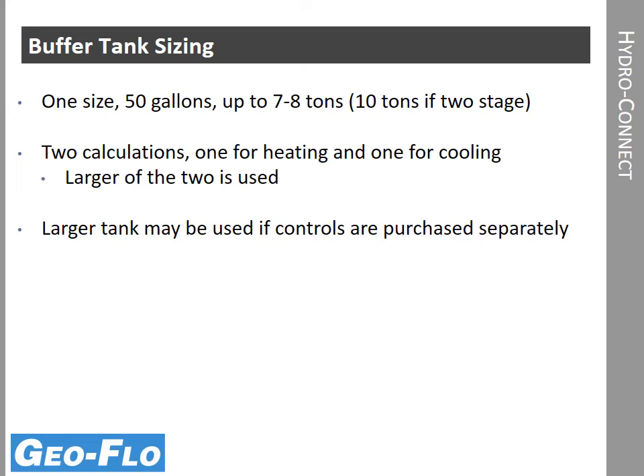So one size handles really a wide variety of applications. It's larger than what we might need for, say, a 3-ton heat pump, but it certainly doesn't hurt anything to have a little bit more storage. The buffer tank itself then is much more universal for other systems. As I mentioned, the buffer tank calculator does 2 calculations, one for heating and one for cooling, and the larger of the 2 is used. If for some reason a larger tank or a smaller tank is needed, the controls can be purchased separately from the HydroConnect system. The tank and the controls can be purchased separately.